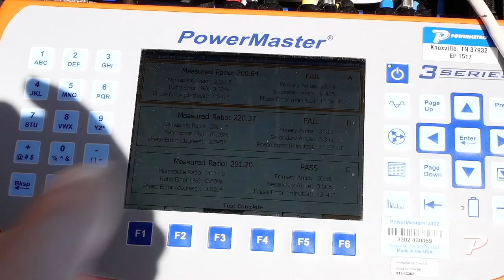And A phase, this is where we talk about these flexes being positional. You got to make sure you get them in the right position. If they're picking something up off of another phase, or they're picking up something loose in there, it can give a phase angle error. So the ratio looks good, but it's a phase angle error. So what Jonathan's going to do is go over here and reposition the A phase flex, move it, and we're going to retry it again.